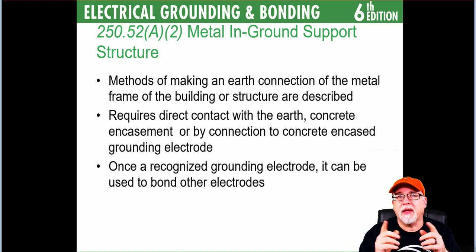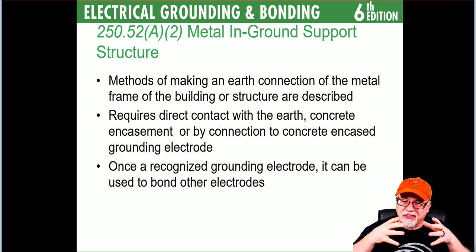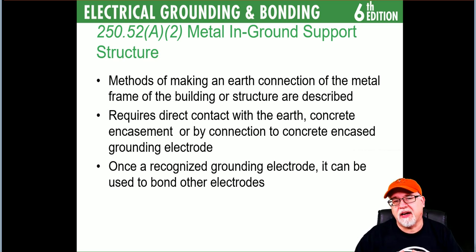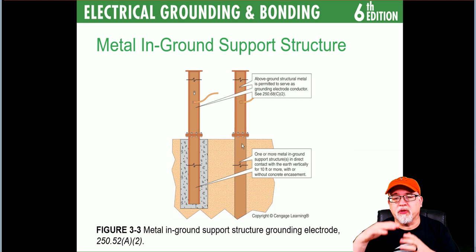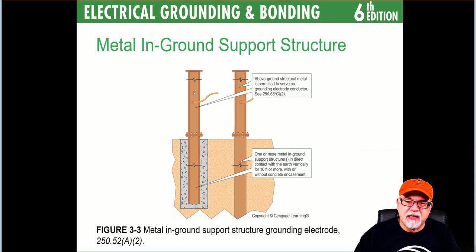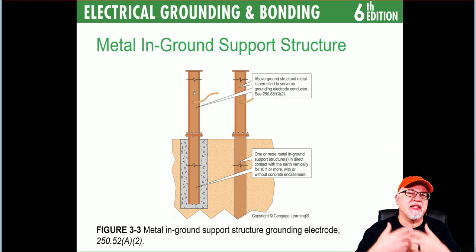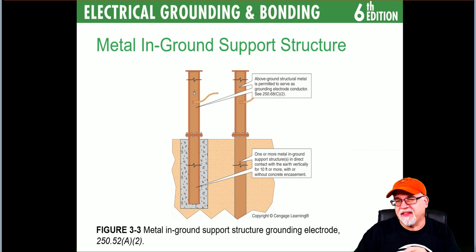This is different from the metal framing of the building — it's the in-ground structural support, actually driven into the ground as a structural support component. It can be concrete encased, and sometimes even longer when driven without concrete. That direct contact with the earth of 10 feet or more, with or without concrete encasing, is what gives it the component that makes it a grounding electrode.